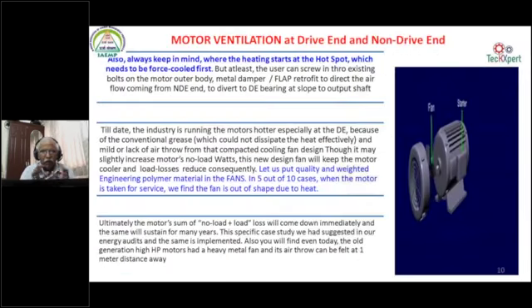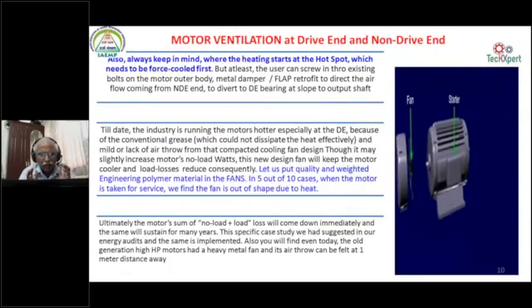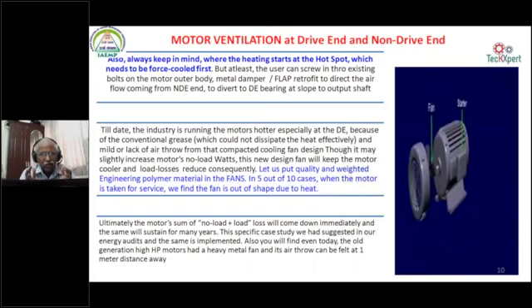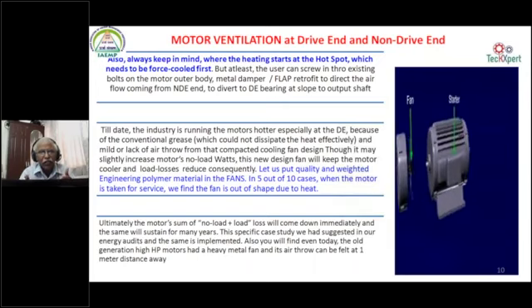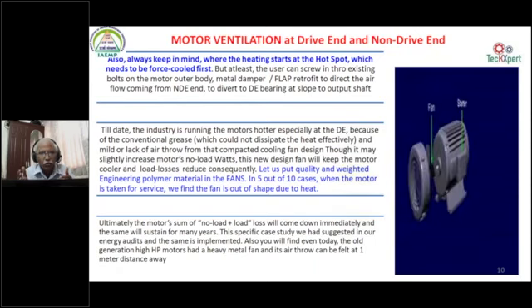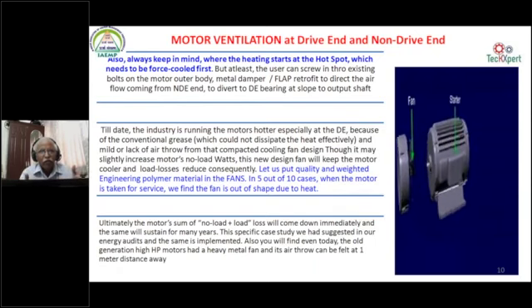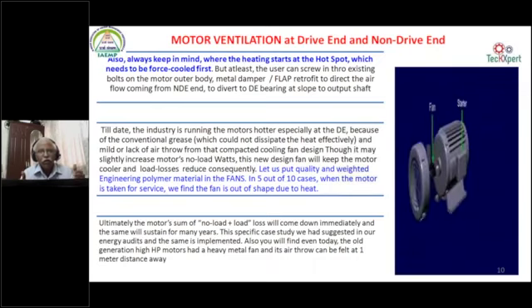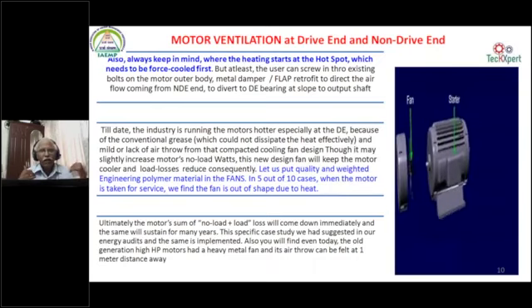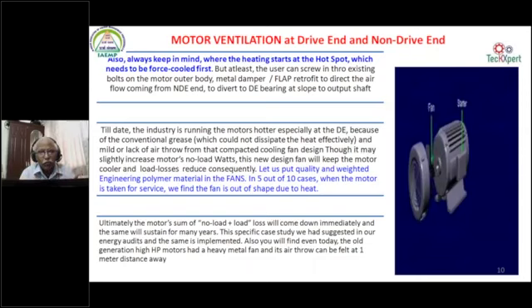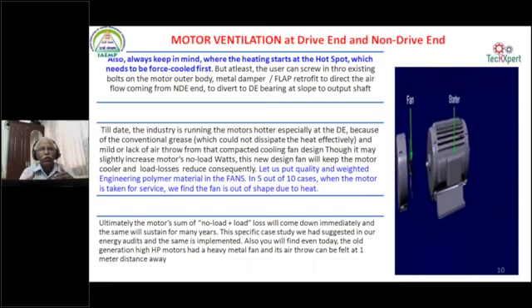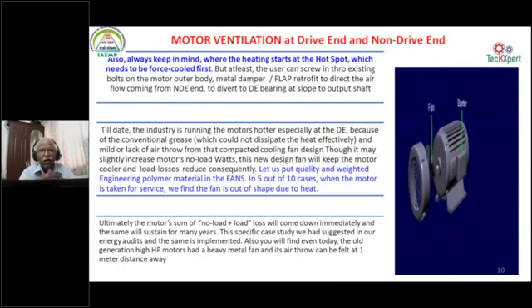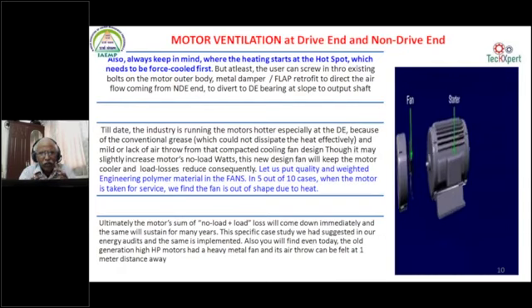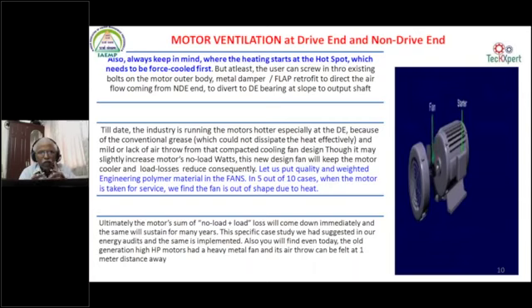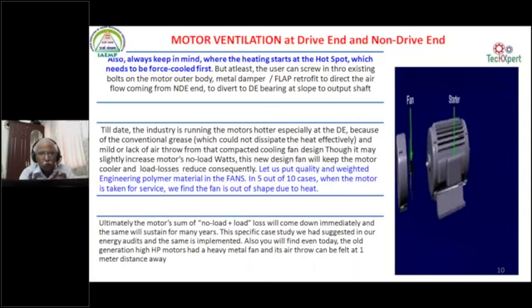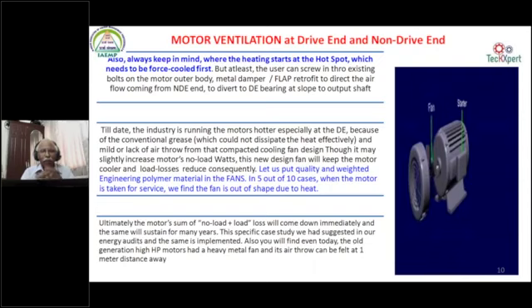The ventilation at the drive end, see, ultimately the hot spot is the drive end of the motor. So you concentrate the air circulation or the air throw coming to the drive end point of the motor. And you can even think of providing a FLAP towards the drive end so that the air is directed from the back of the motor, from the non-drive end to the drive end of the motor, sloping towards the shaft of the motor, so that there is always an active, positive cross ventilation across the drive end of the motor, so as to withstand the hot spot of the given bearing area or the drive end area.